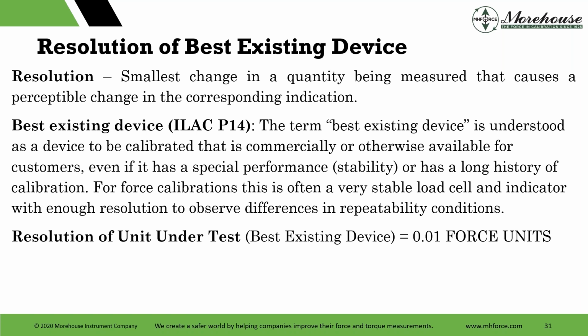You know, if you're doing this for force calibration, I see people all the time use junky load cells or devices that aren't as good, and then they do not get good numbers off of their equipment. So what I say is, very stable load cell and indicator with enough resolution to observe differences. That's the other thing. If we had a 2,000 pound load cell and we set the resolution to 20 pounds, I would imagine it's going to be perfect. And that's not going to be that many counts now, is it? It's only 100 counts. So we're going to have a problem if we do that. So we want to have enough resolution as well. For the test I did, the resolution was 0.01 force units.